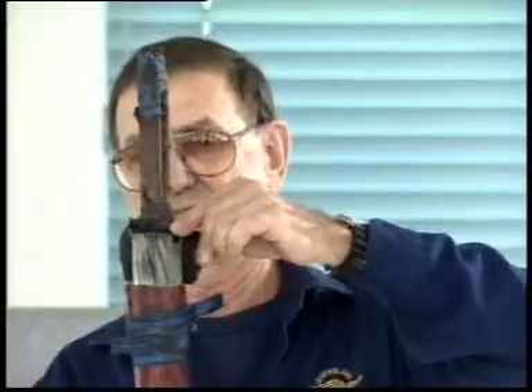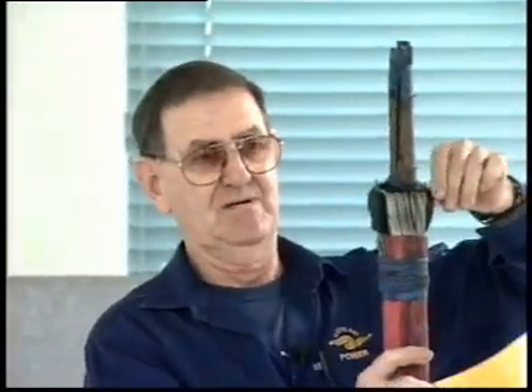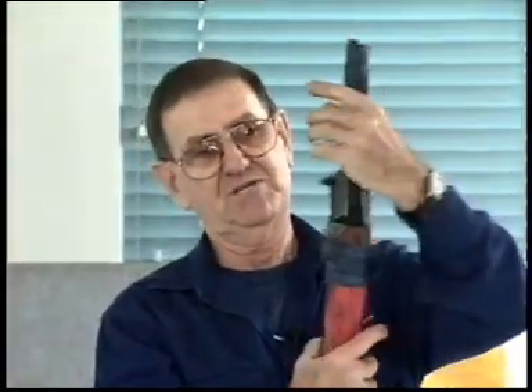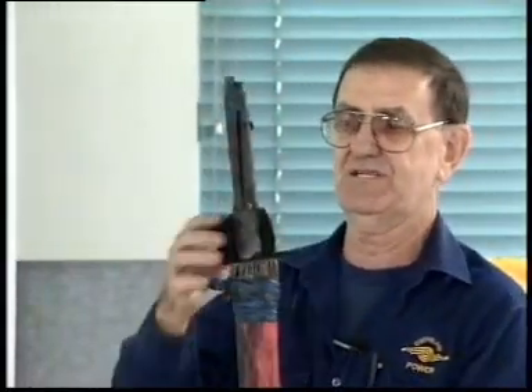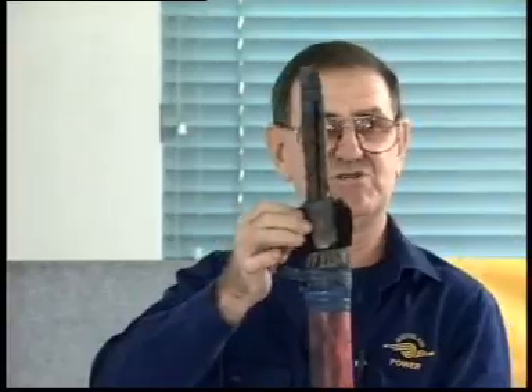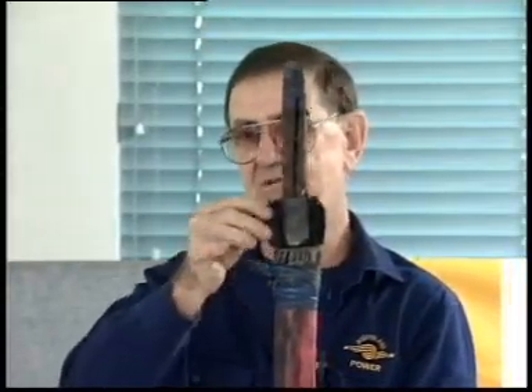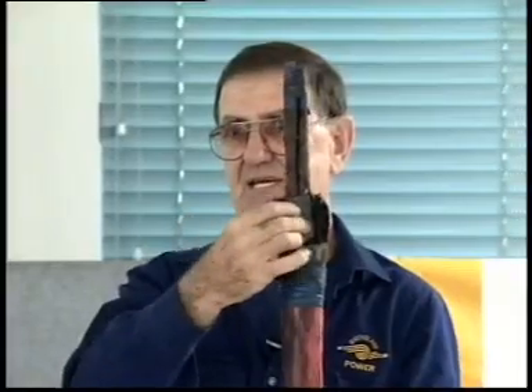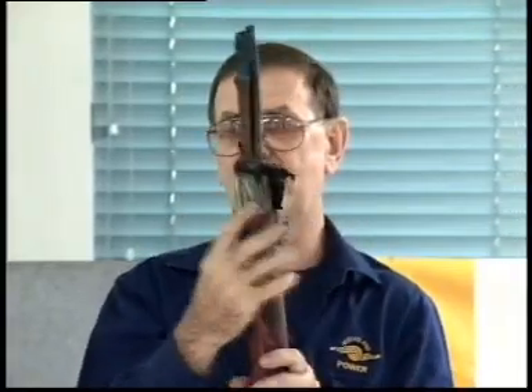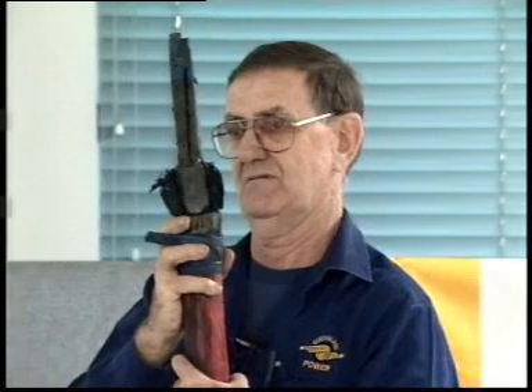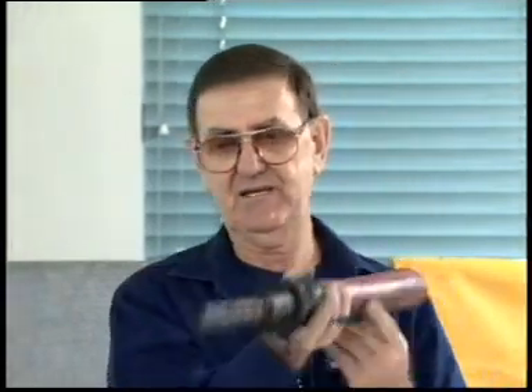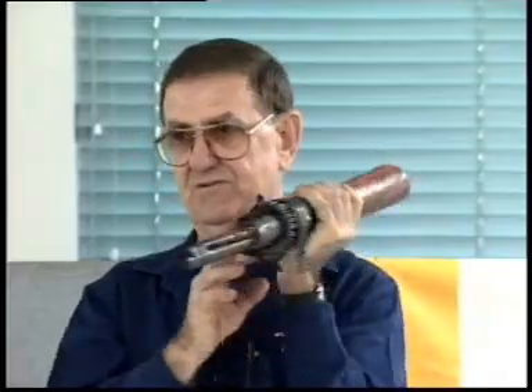have this bitumistic hessian, for a better word. Now underneath that bitumistic hessian we've got lead. Now that lead is in one continuous pass, one continuous tube throughout the full length of the cable, and the reason that bitumistic hessian is there is to protect the lead and to stop the steel from abrading on it as well. Now underneath the lead, on the inside, we've got 3 conductors, 11,000 volts.